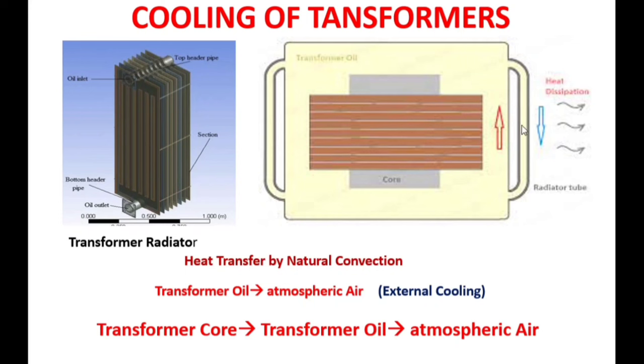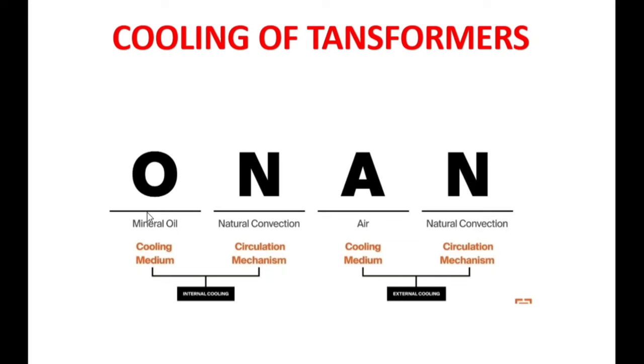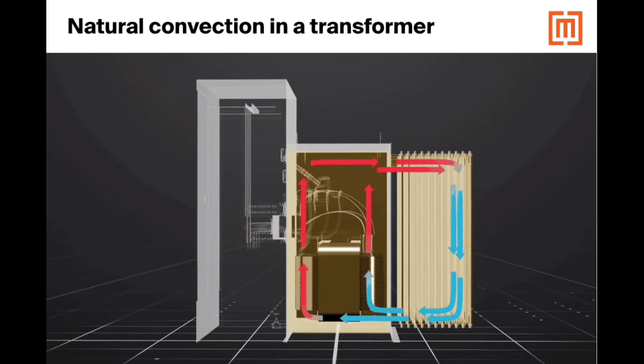The transformer oil dissipates its heat to the surrounding atmospheric air whenever the air contacts the cooling tubes. Surrounding air receives heat from the transformer oil; transformer oil loses its heat to the surrounding air. In this way, external cooling maintains the optimum temperature of the transformer. Heat is transferred from the transformer core to the transformer oil, then from the transformer oil to the atmospheric air. These transformers are known as ONAN type transformers — O stands for mineral oil (transformer oil), N for natural convection internally, A for air, and N for natural convection externally.